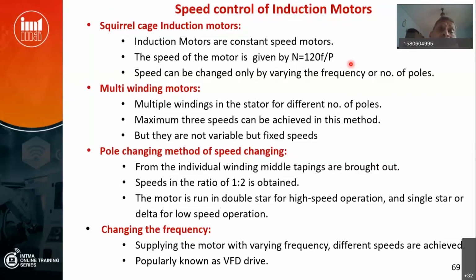How do we get a different speed from this motor? First, depending on the number of poles, as per this formula, you can get different speeds. A 2-pole motor with 50-cycle supply gives 3,000 rpm. A 4-pole motor gives 1,500. So you can have multiple windings in a motor, but how many can you have? Maximum 3 windings, otherwise the motor size will become huge. Practically 2 to 3 windings, for different poles, housed in a motor.